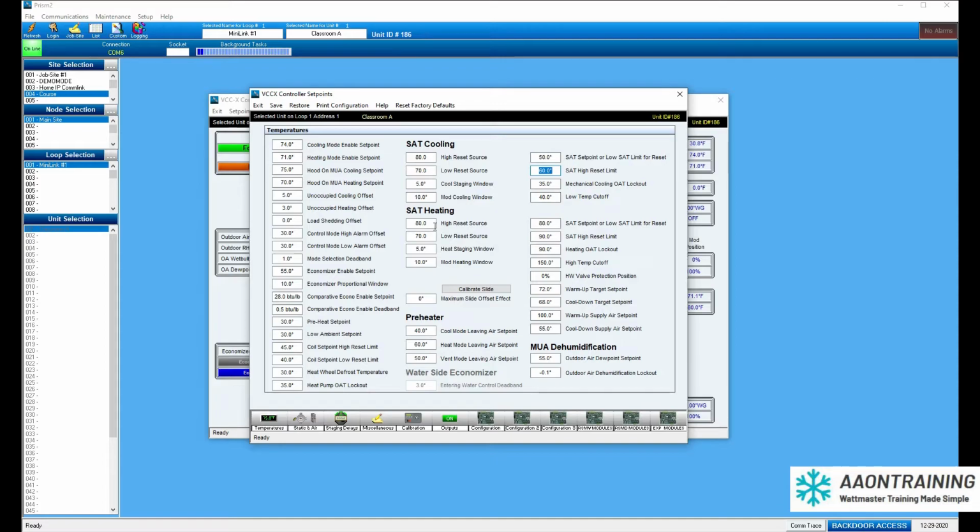Same idea here. If the space is quite hot, well, we really don't want to deliver a lot of heat, so we're going to just give you 80 degrees. But if the space is a little on the cooler side, well, maybe we want to give you 90 degrees. The key is that these are dynamic ranges. So if it was 75 in the space, you'd be delivering 85-degree air, which is quite nice.